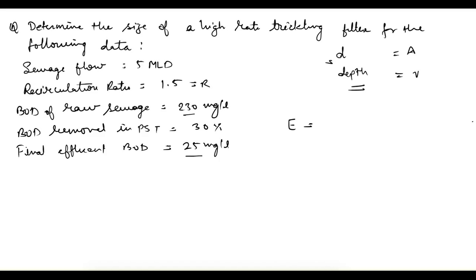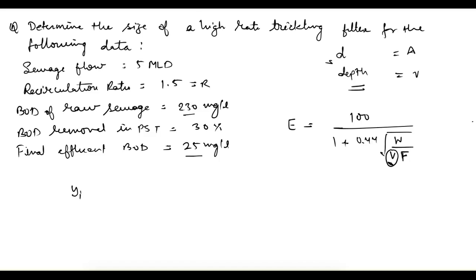For volume, recall the NRC formula for efficiency: E = 100 / [1 + 0.44 × √(W / (V × F))], where W is the BOD load in kg/day, V is volume, and F is the recirculation factor. This formula includes volume, so we can use it to obtain V. We also need efficiency, which can be found from: E = [(BOD of influent − BOD of effluent) / BOD of influent] × 100.